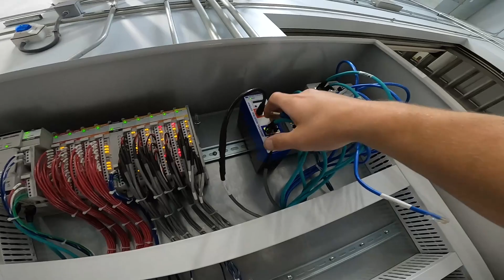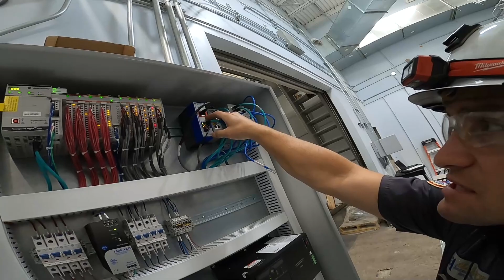Kind of neat here - if you look on top, you can see the Danfoss probe way up there, and on the recirculator you have another Danfoss probe here. So that's where you've got to program - you have to cut your cables a certain length, measure those cables, and then once you get them measured, you can program your 4 milliamp and your 20 milliamp set points, which will offset your dead zones. Quickest way to explain it, you can pull up the manual. Here's the control system here - can't really show you because it has the customer's name on it, but you can see this.